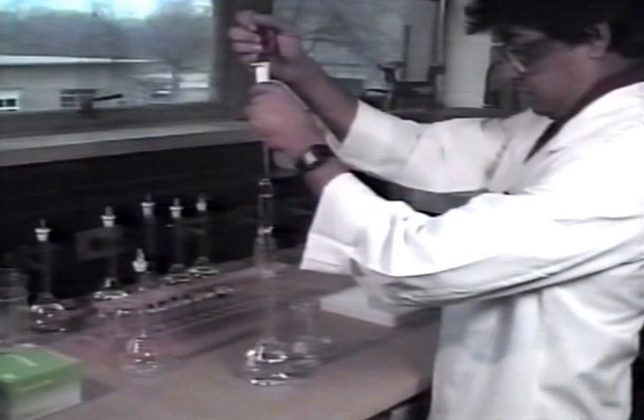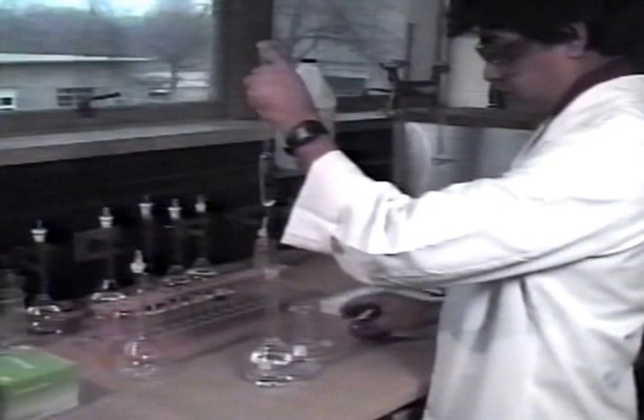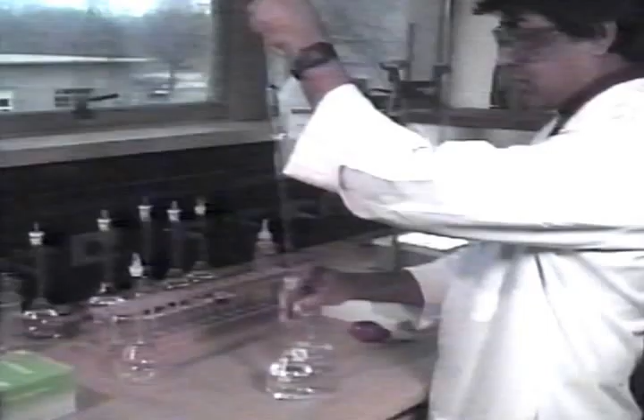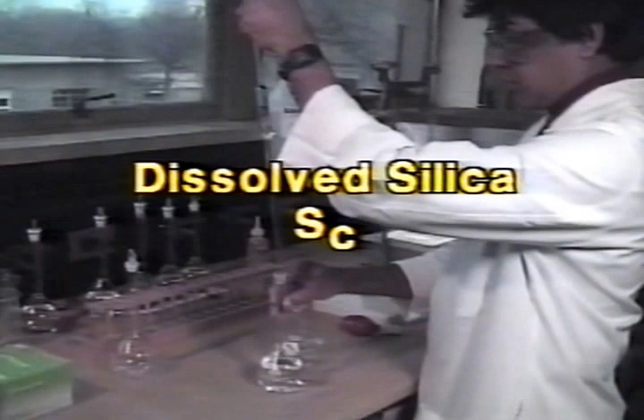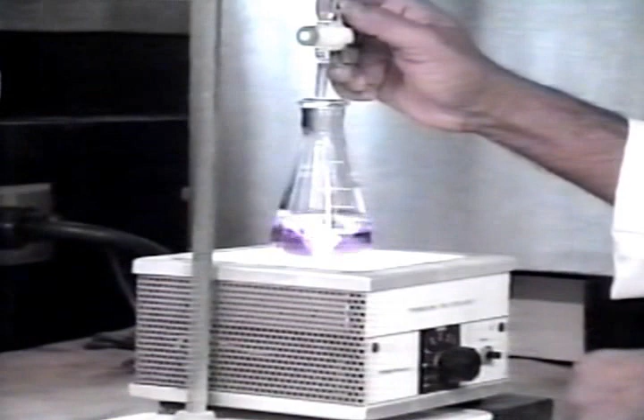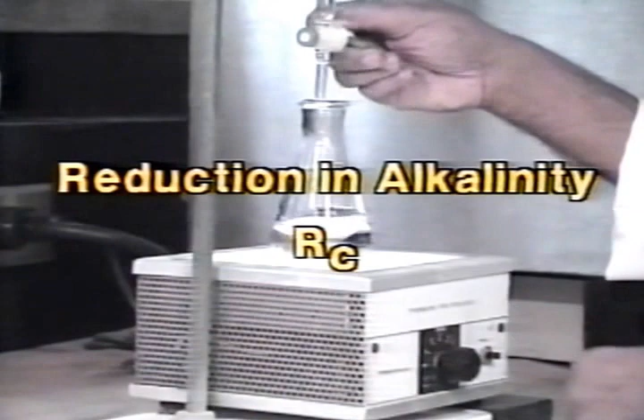A portion of the liquid passing through the filter is analyzed for dissolved silica using either a gravimetric or photometric method. The details are found in the ASTM method. The quantity of dissolved silica determined by either of these methods is termed S sub C. Another portion of the liquid is placed in a flask and titrated to an endpoint with phenolphthalein. The titration is complete when the liquid turns clear. The reduction in alkalinity is then calculated. This is termed R sub C.